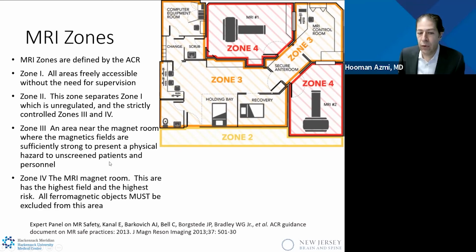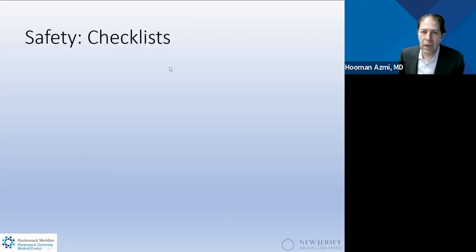And then zone 4 is the actual magnet room. This is where the fields are the highest, and all ferromagnetic objects must be excluded from this area. And as you know, we don't even allow much ferromagnetic objects into zone 3 for safety reasons. So checklists have been demonstrated in multiple fields to increase safety. So we have several checklists.